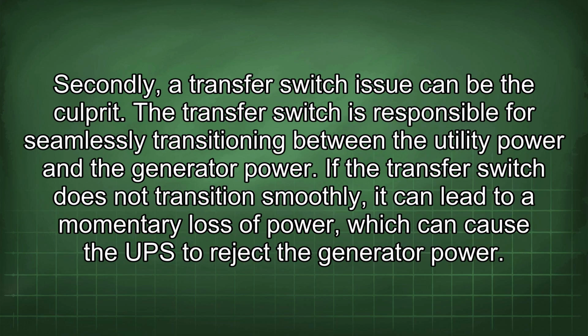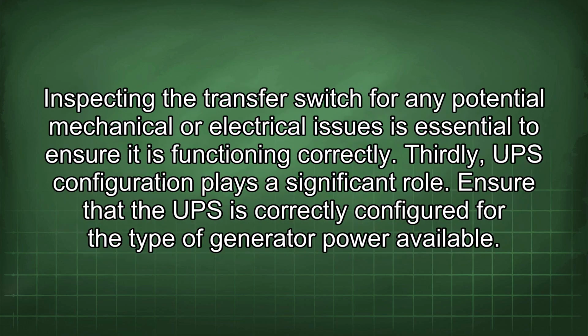Secondly, a transfer switch issue can be the culprit. The transfer switch is responsible for seamlessly transitioning between the utility power and the generator power. If the transfer switch does not transition smoothly, it can lead to a momentary loss of power, which can cause the UPS to reject the generator power. Inspecting the transfer switch for any potential mechanical or electrical issues is essential to ensure it is functioning correctly.